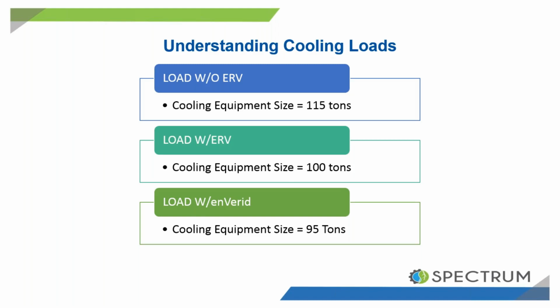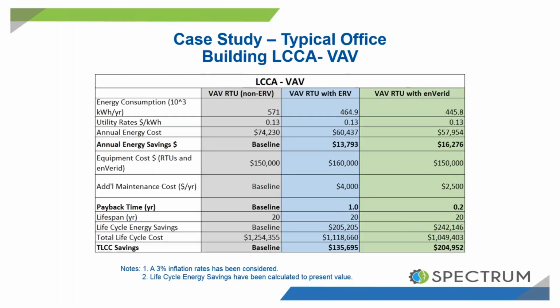They calculated loads without ERVs, where the cooling equipment would have had to be 115 tons. Load with ERVs, where the equipment sizing could come down to 100 tons, or load with enVerid and no ERV, and the cooling equipment size was able to be downsized to 95 tons. So about a 20-ton reduction versus traditional equipment sizing without an ERV, and a decent improvement versus traditional energy recovery.